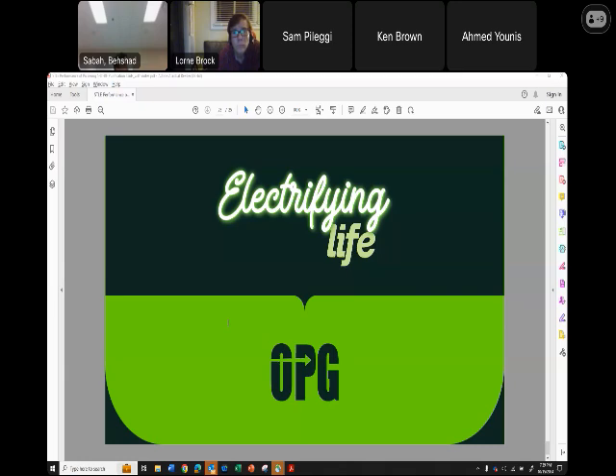So the only thing you can actually do in the absence of system design, which is your hands are tied, is five times more fluid maintenance. ASTM D8323 is the standard for EHC fluids. It's the in-service guide for the maintenance and testing of phosphate ester fluids. It's a great standard. Anybody that's testing or using these fluids should have a copy of that. It's $68.